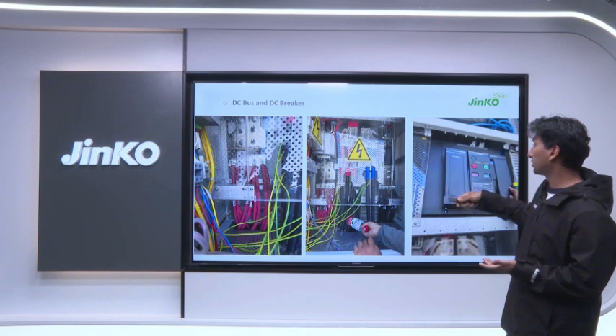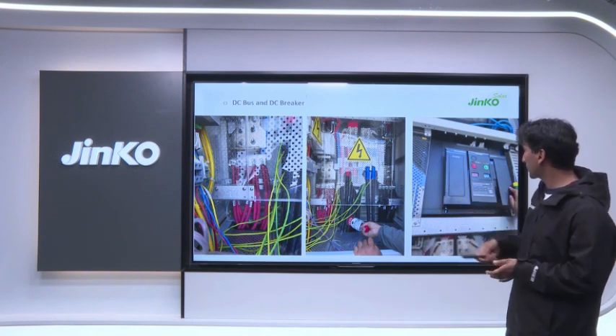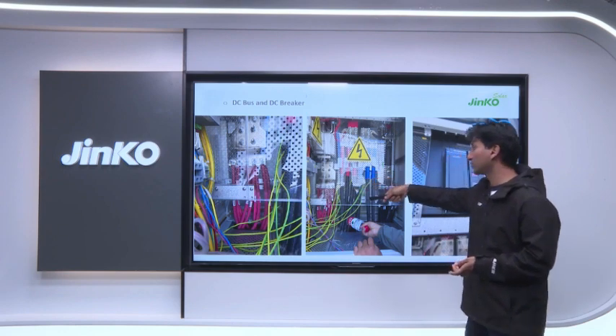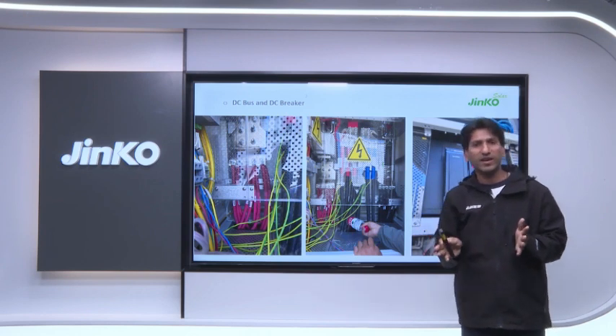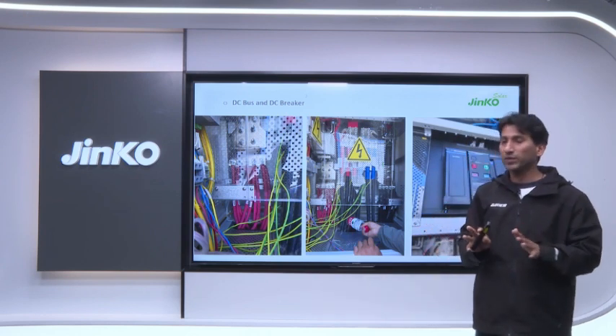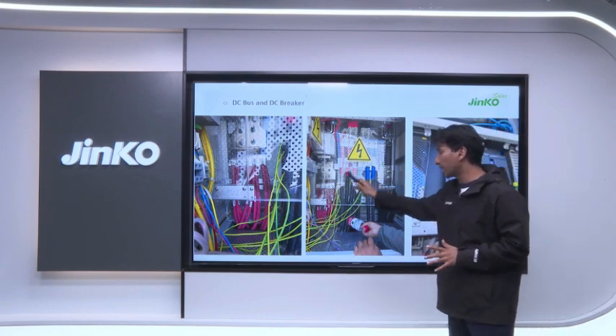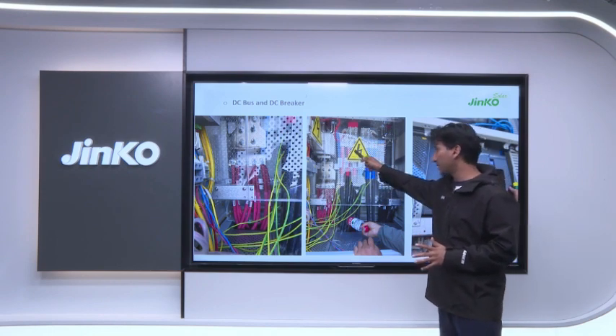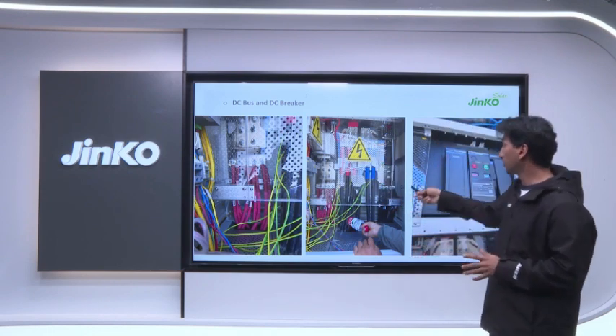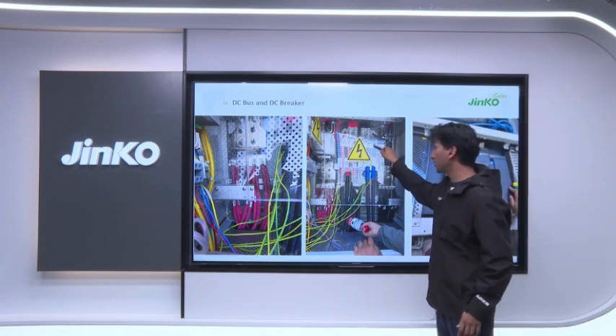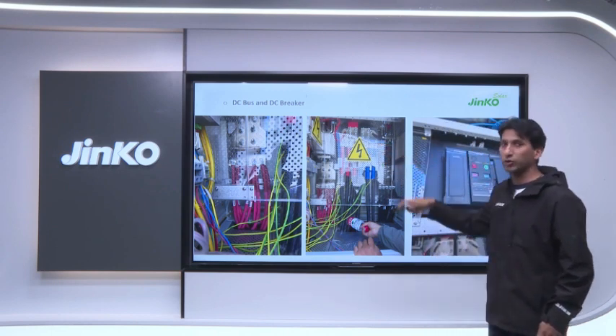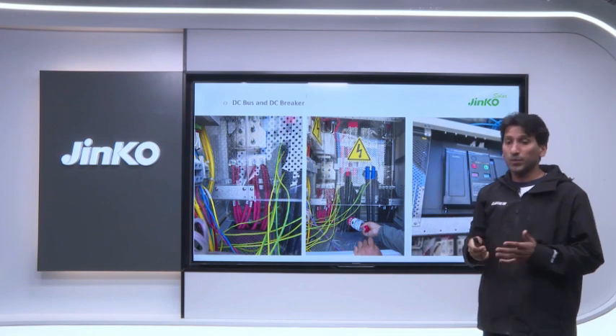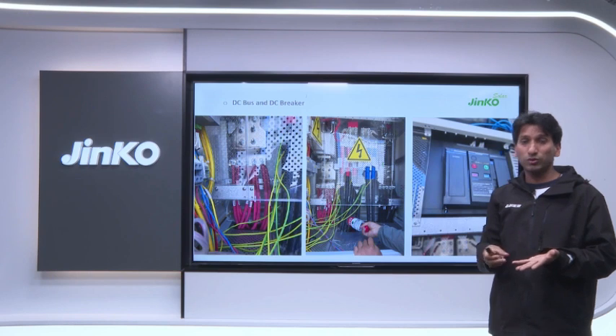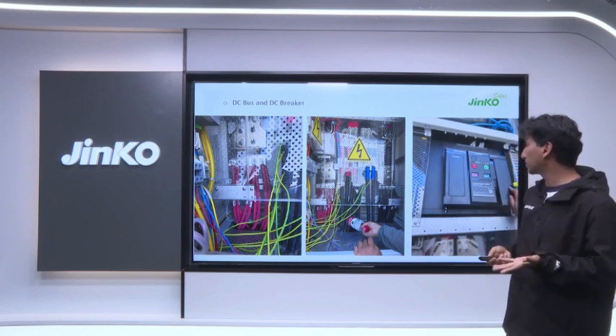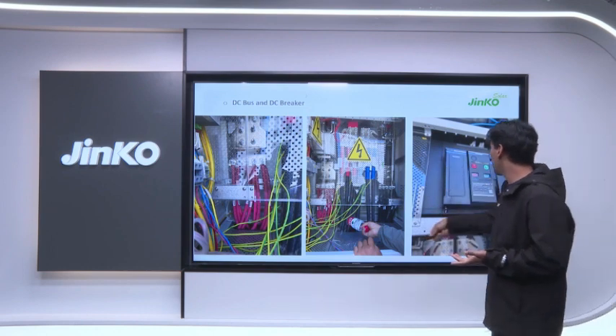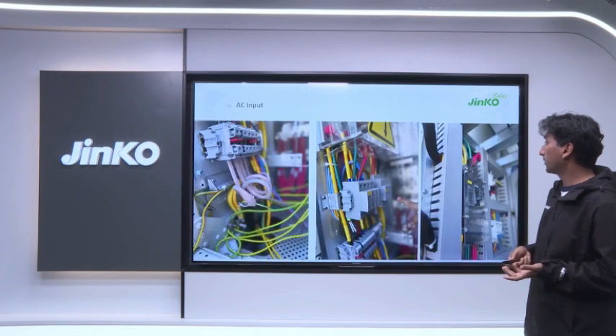This is a closer look at the DC bus bar and DC breaker. If you see here, the DC bus bar is behind this, which is already connected when the container leaves. Most of the connections inside the container have already been done in the factory. The only things that need to be done are connecting the AC power supply and the DC cables, and then connecting to the PCS. So these are already connected. We only need to connect the output DC cables, and then connect to the PCS. The size of this cable depends on the size of the project and also on the PCS we are using. So this is the DC part.